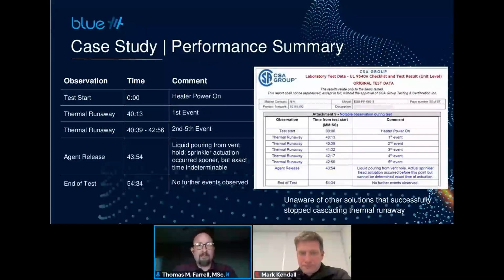And if it can't be stopped because of its configuration, if I had 50 cells in parallel and they were all unfused, so that if one goes into thermal runaway, it shorts the rest and they're all going in, this product would still be able to manage the heat load coming from that particular hazard. And again, NFPA 855 has acknowledged that it's novel and that it can be effective. And language is going to be included soon that will start to talk about how to apply systems like this that aren't more traditional fire suppression systems.